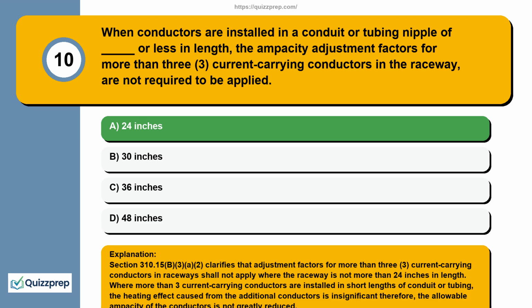Section 310.15, b. 3a. 2, clarifies that adjustment factors for more than 3 current carrying conductors in raceways shall not apply where the raceway is not more than 24 inches in length. Where more than 3 current carrying conductors are installed in short lengths of conduit or tubing, the heating effect caused from the additional conductors is insignificant, therefore, the allowable ampacity of the conductors is not greatly reduced.